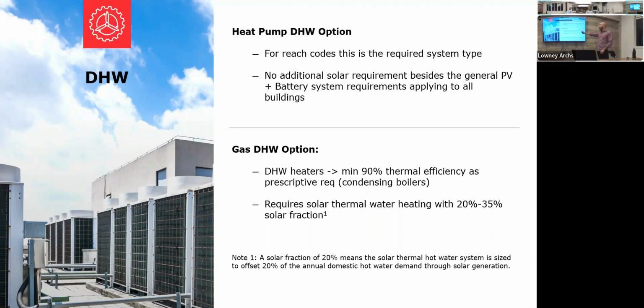You have the option to use gas if you're in a city that doesn't have that electric REACH code. Again, that equipment needs to be 90% efficiency, which needs to be a condensing boiler. And on top of that, you have to provide additional solar capacity with your heater. So in addition to what the code requires, you have to add additional solar. Actually, it has to be solar thermal. There used to be a PV equivalent requirement option for electric, but for gas, you don't have that. So it requires even more solar.